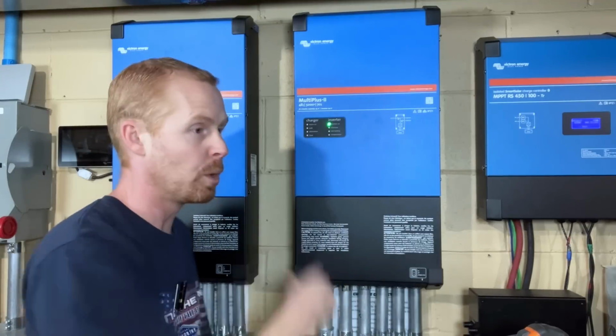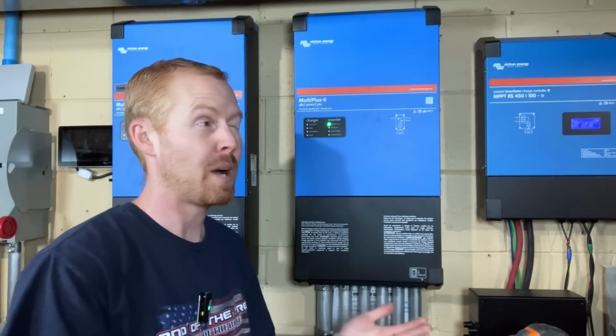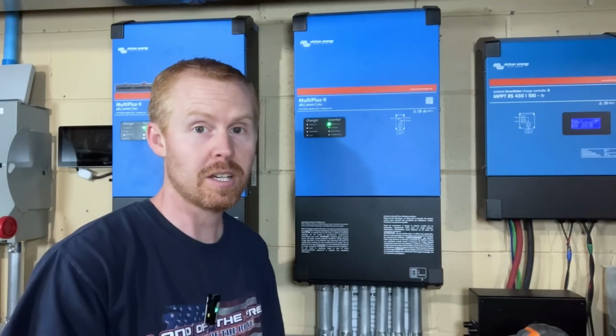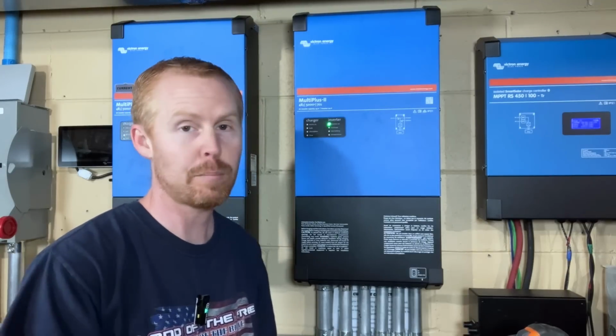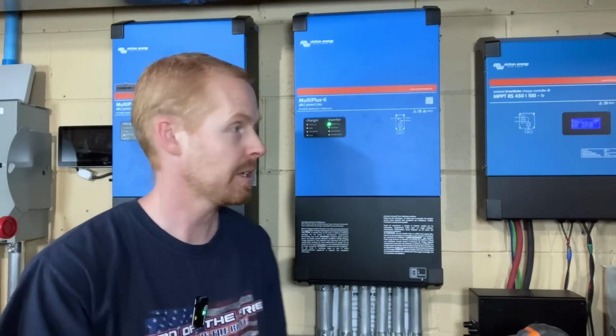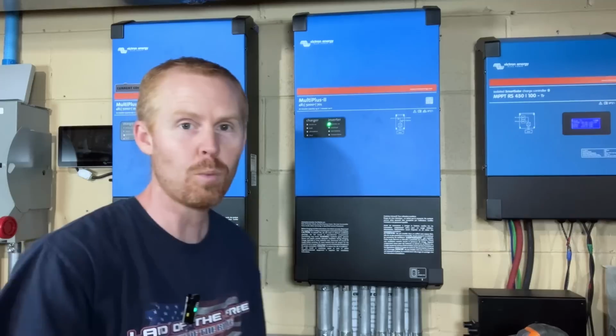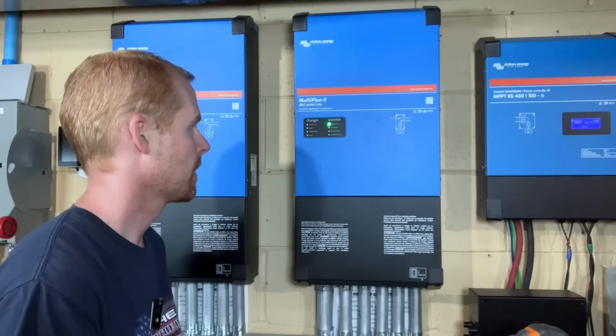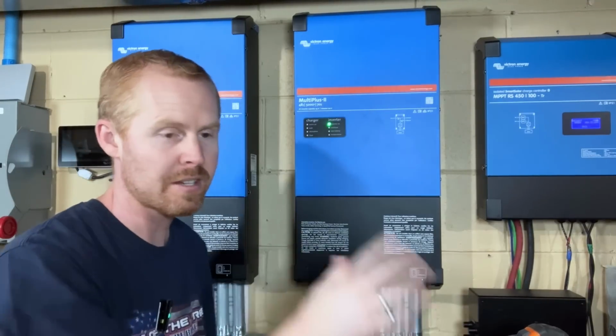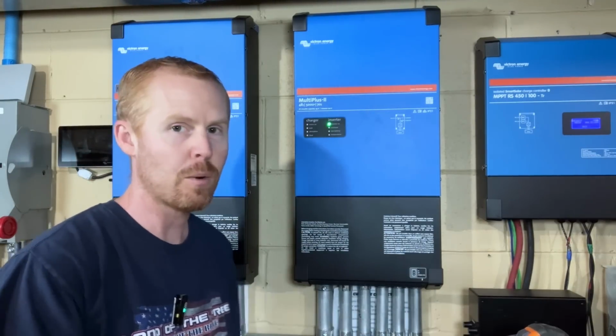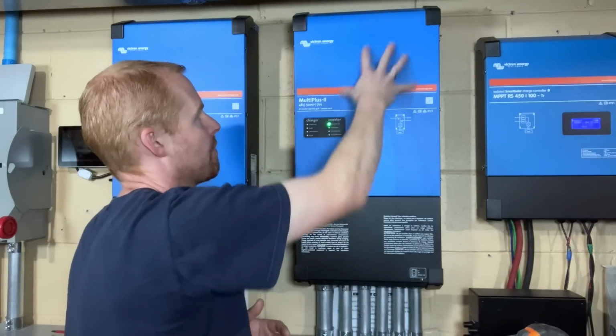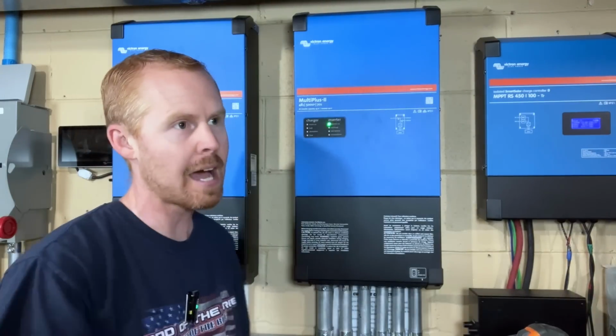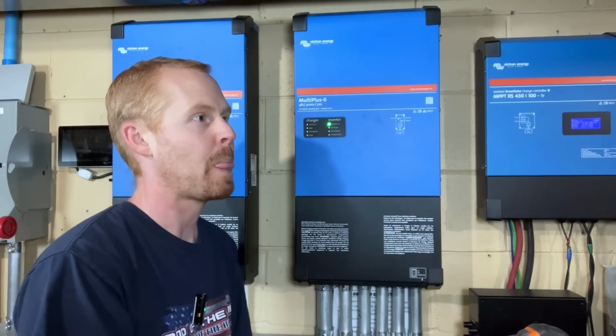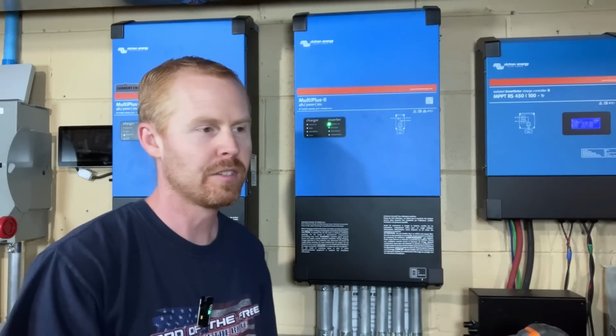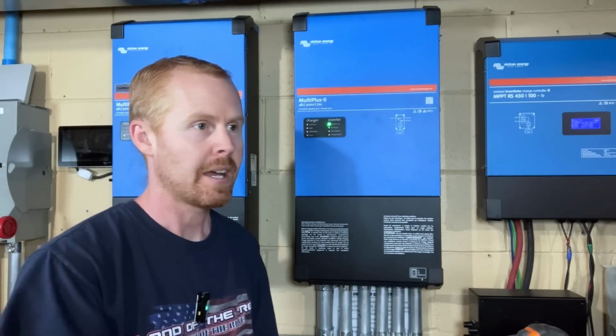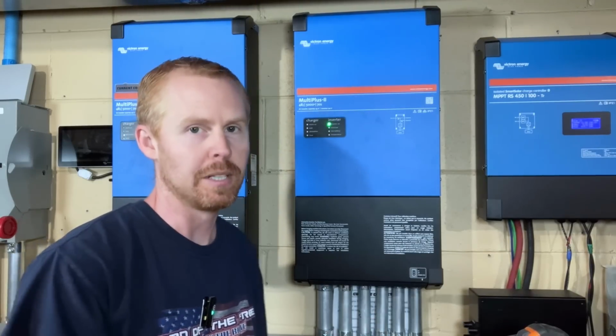These do allow me to save about 3.2 kilowatts in idle consumption in a 24-hour period. These have about 15 watts idle consumption. They do have, as I stated earlier, less power output, but because they have the toroidal transformer in the top, they have a better handling of inductive loads and a better surge ability.